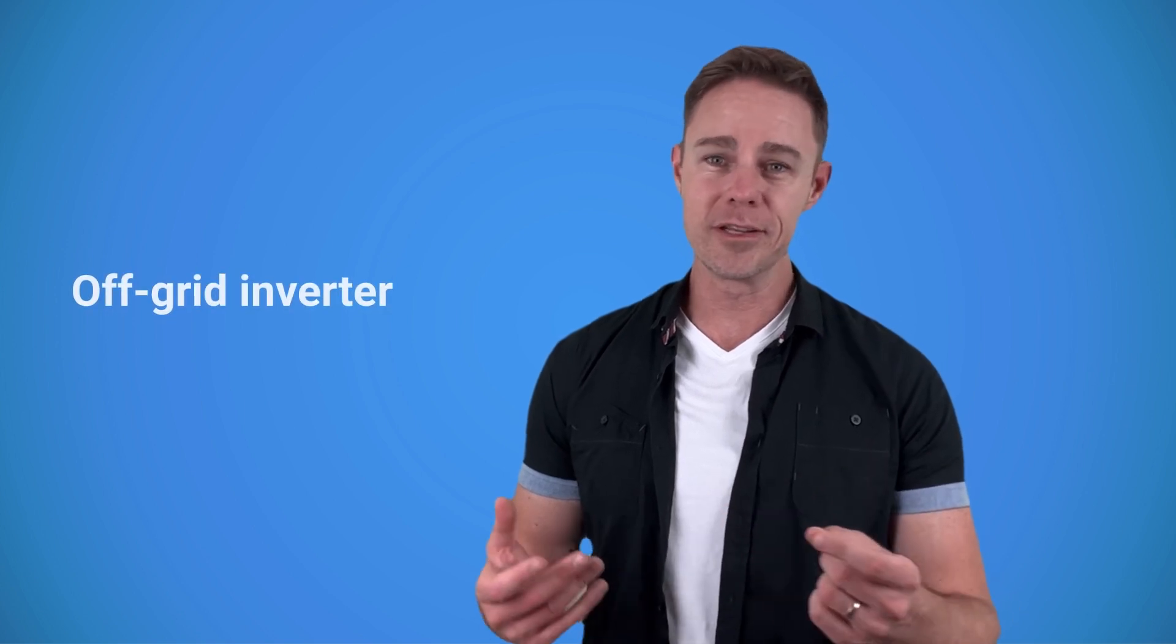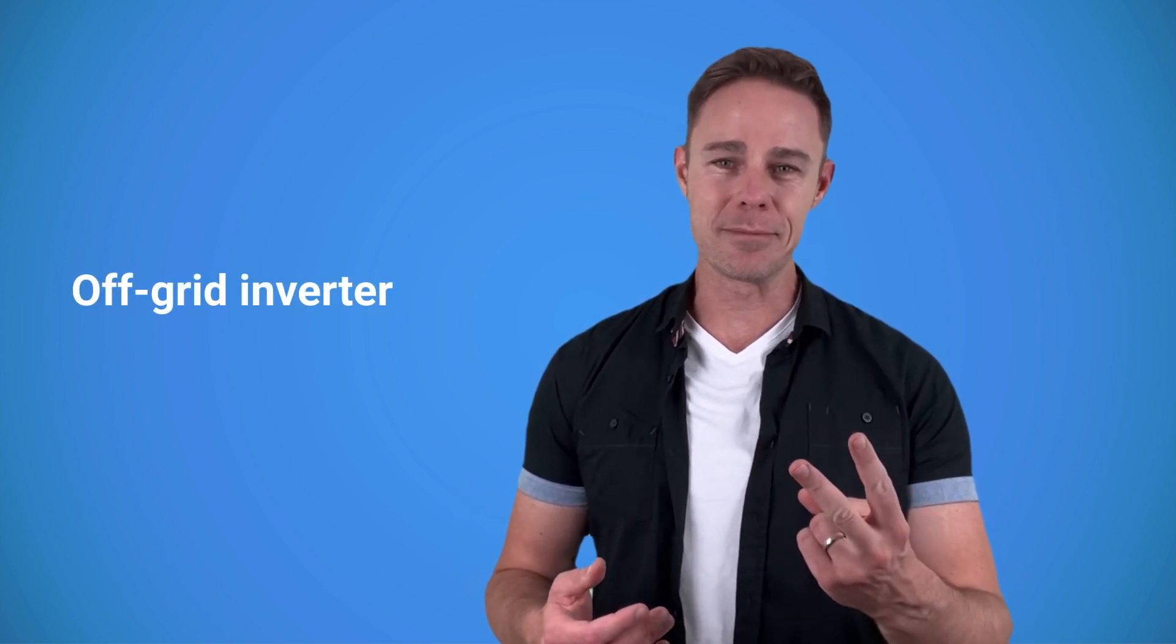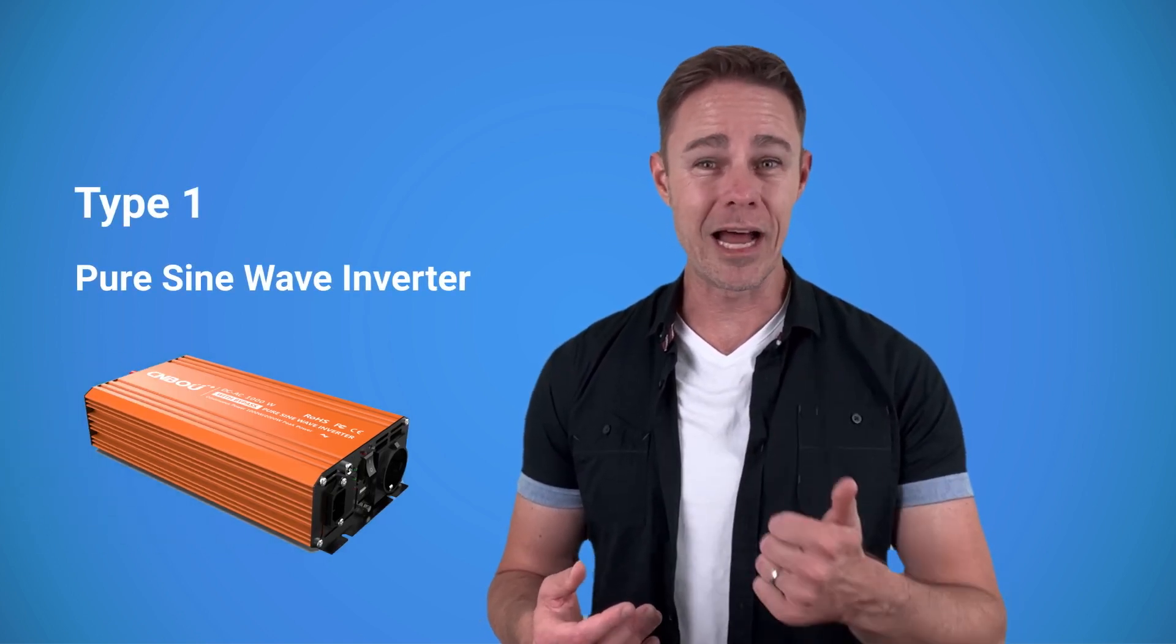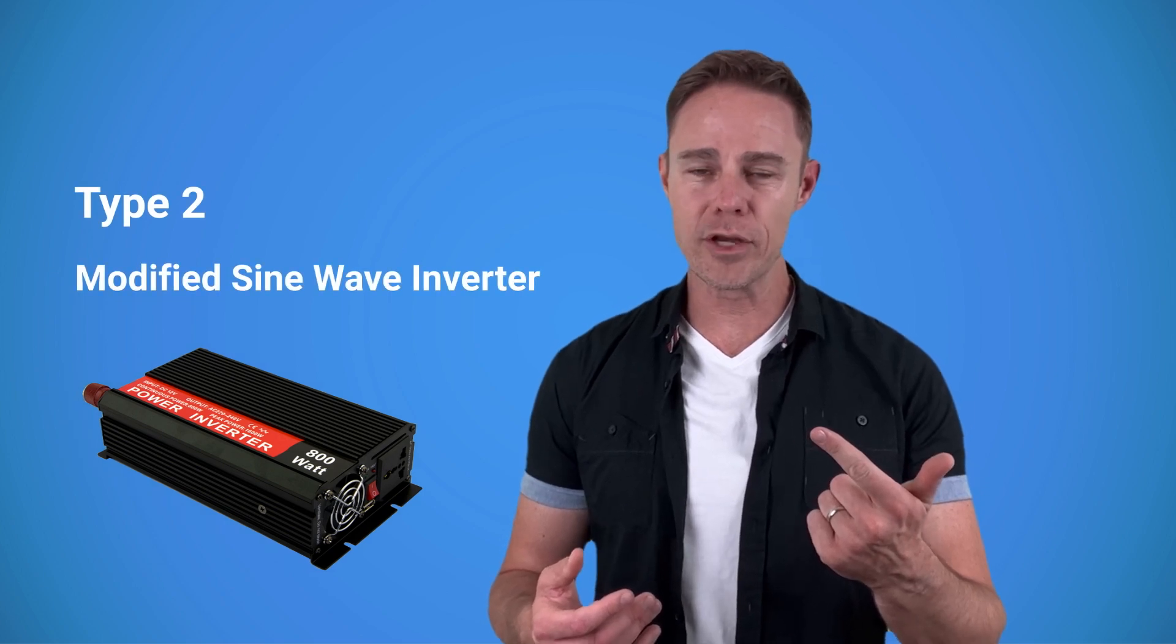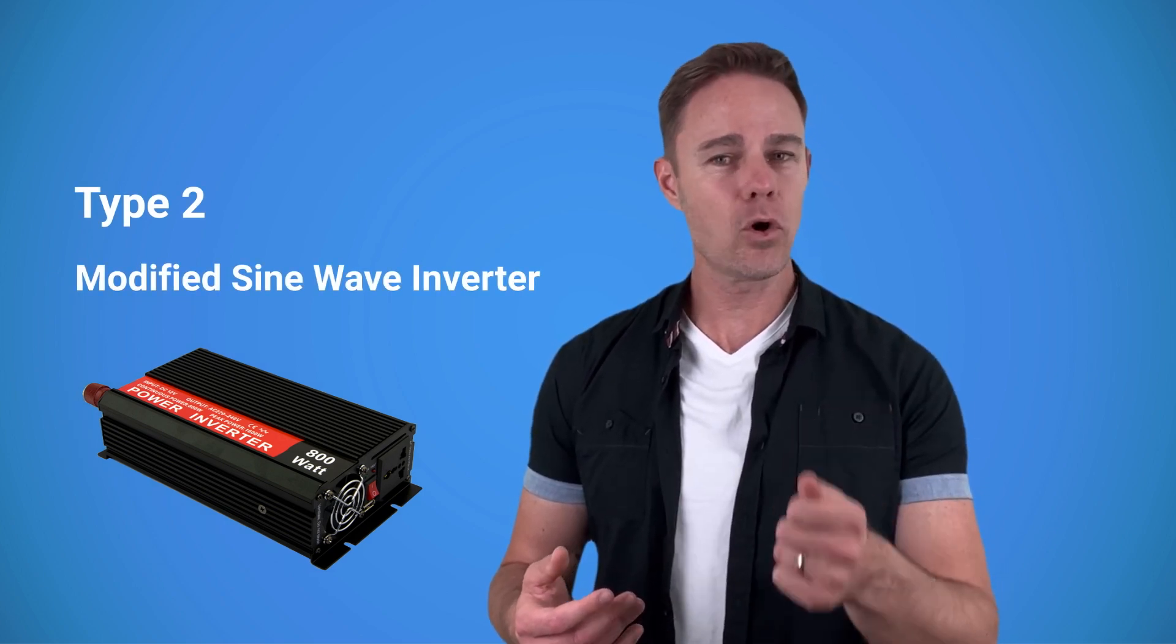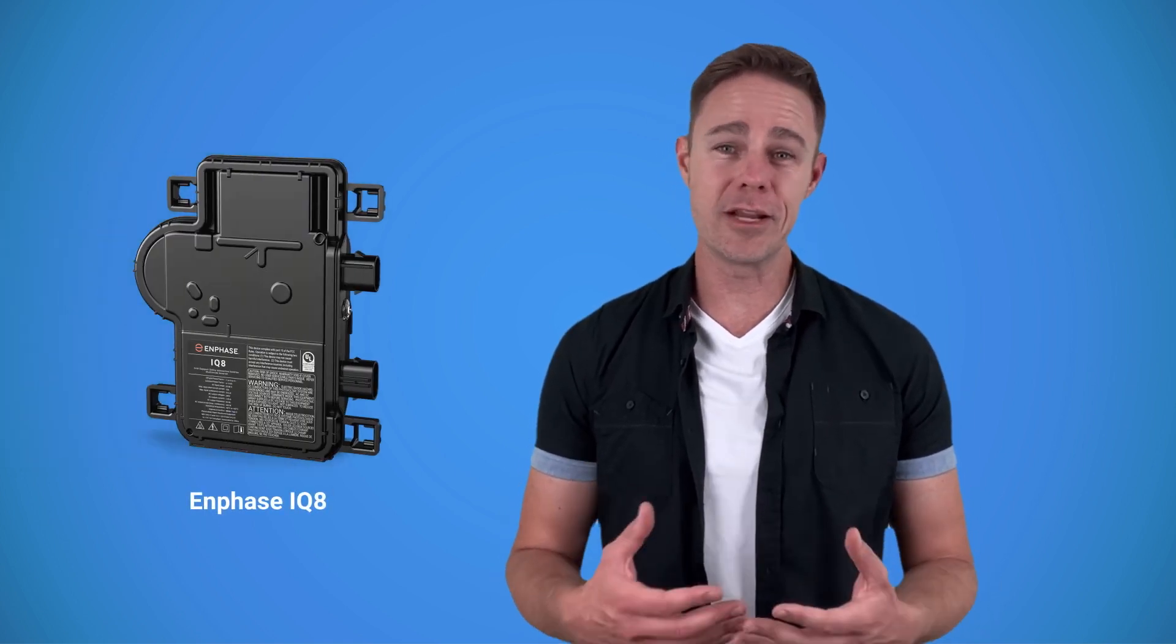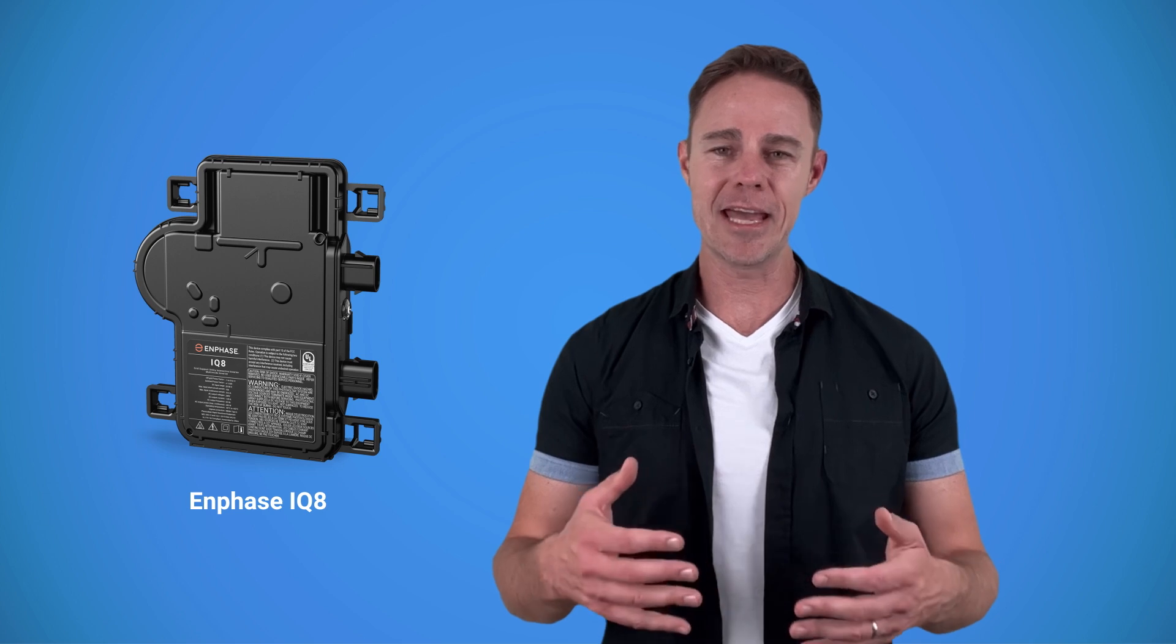For this configuration you would need an off-grid inverter. There are two types that are commonly used: the pure sine wave inverters that produce cleaner and more reliable electricity, and the modified sine wave inverters which are cheaper but can cause interference. For example, a radio may buzz a little when it's turned on. They're also not suitable for sensitive electronics such as medical equipment. The latest models of micro inverters such as the Enphase IQ8 can also be used in off-grid and hybrid systems, but again they can only support AC batteries.